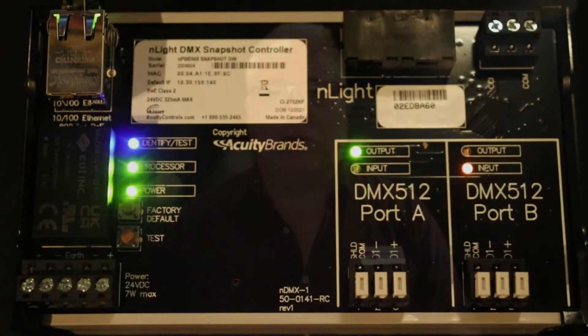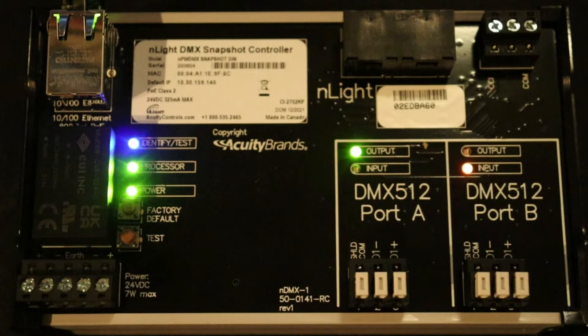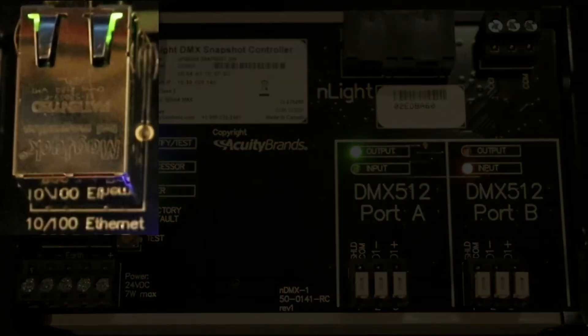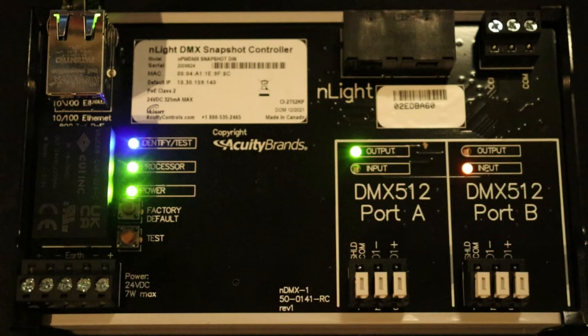I'm going to be showing you specifically what it looks like in Sensor View and in Pathscape and the different bits that you will see on the hardware. Quick overview of the hardware: on the top left side you have the Power over Ethernet connection which you will use to see the device with Pathscape. If you're not using PoE, down in the lower left you're going to have to give it 24 volts, but you can use PoE to power up.